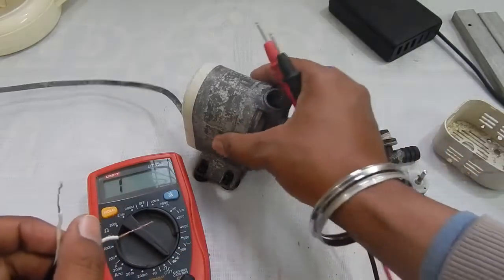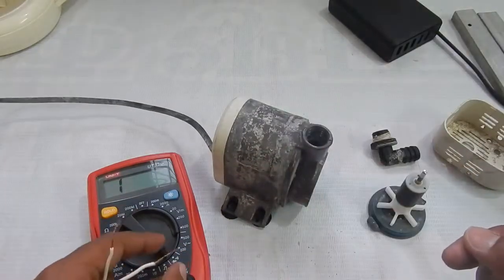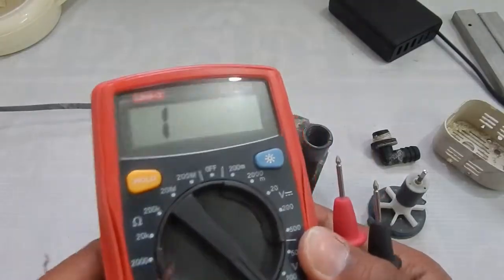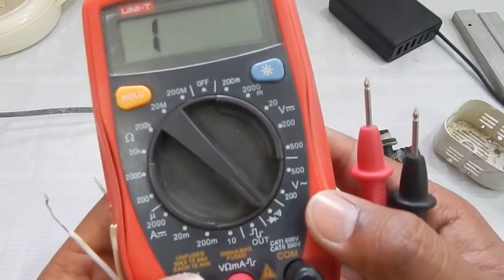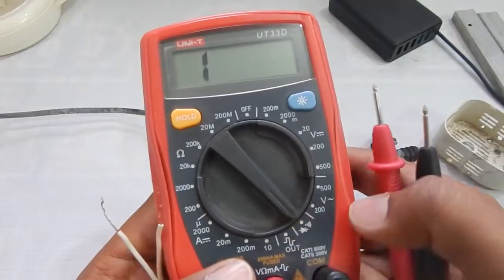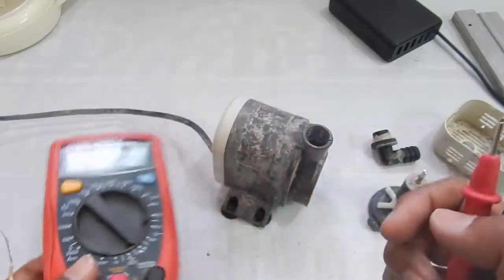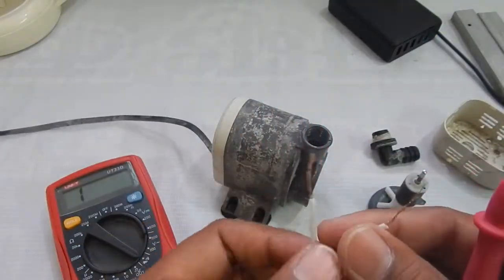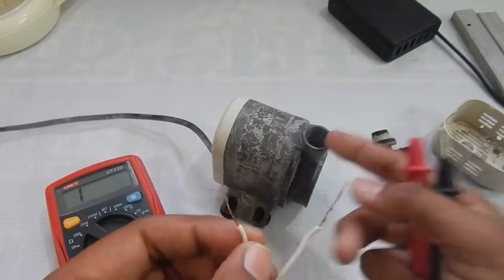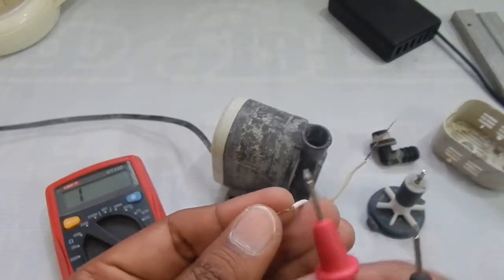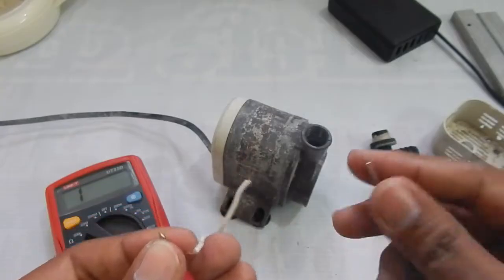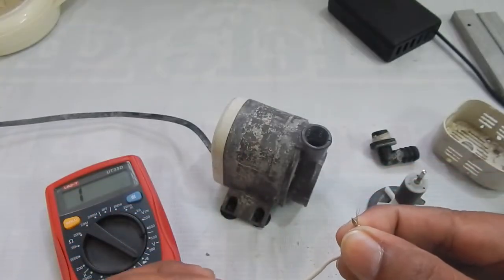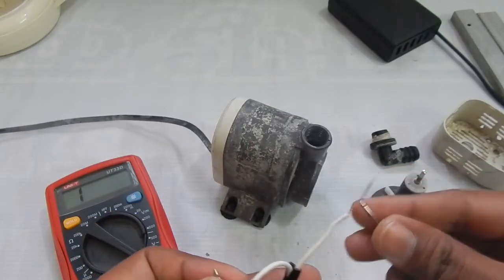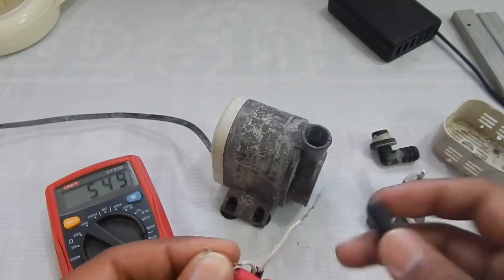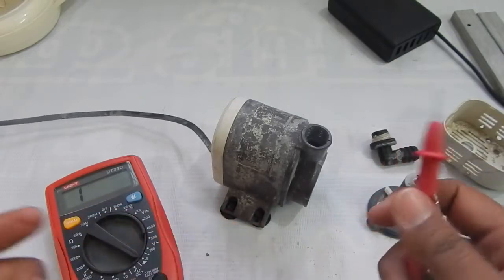So what you need to do is basically turn your multimeter into the continuity setting, and then there are two wires coming out of it. If the pump is shorted out in the middle, you can put one probe on one wire and one probe on another wire. You can see we are not getting anything, and we are also not getting a beep, so the pump is definitely not shorted.